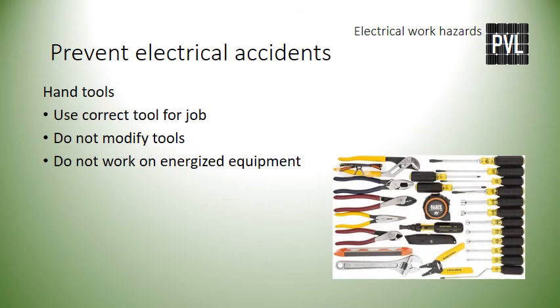Hand tools selection can prevent severe hand injury. Hand tools should be used for the job they were designed to do — do not improvise or modify hand tools or the way they should be used. Use quality tools that are in good condition — worn or broken tools can cause injury if they fail during work. Insulation on electrical hand tools should be present and undamaged. Do not work on energized equipment if at all possible, but if absolutely necessary, use proper voltage-rated insulated hand tools and use extreme care not to touch live parts.